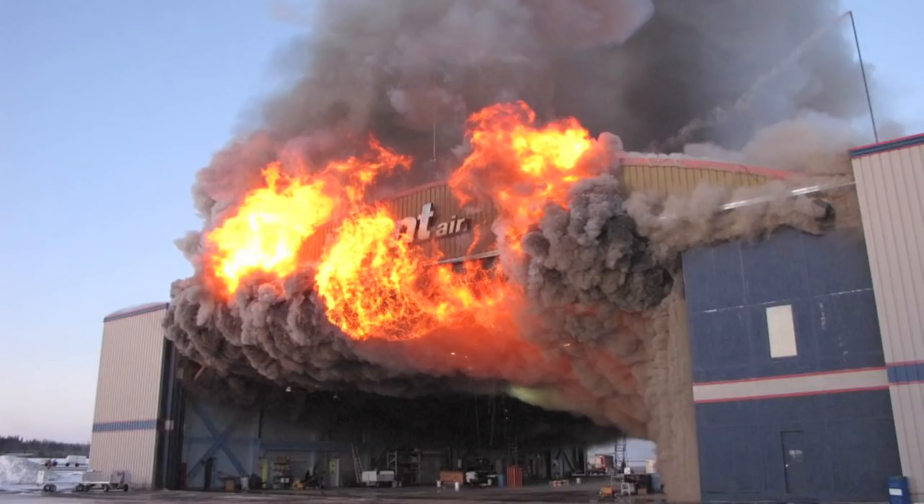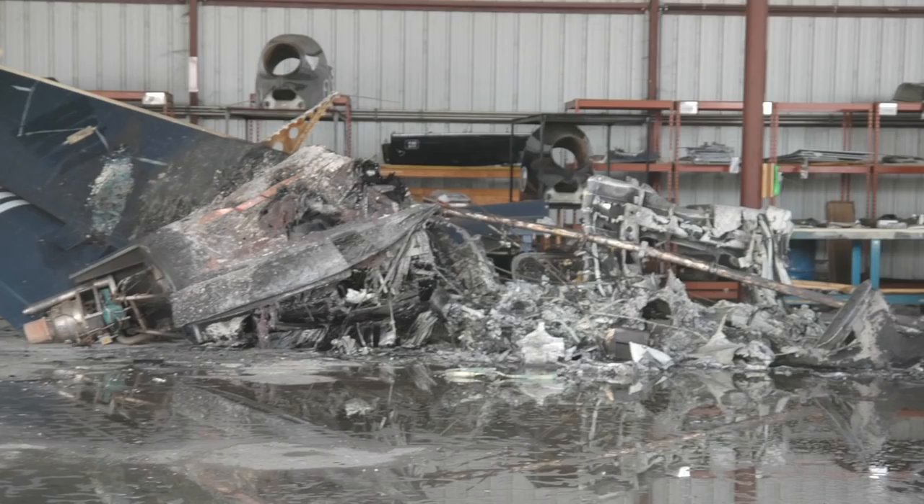The risk of fire damage to aircraft in hangars is well documented. Tests conducted by the FAA and others show that an aircraft fuselage skin can fail within 45 seconds of fire exposure. Since the value of any aircraft inside the hangar will often be several times the value of the hangar itself, the primary goal was to suppress any fire before fuselage failure occurs.